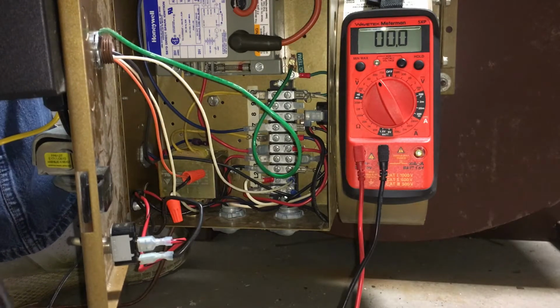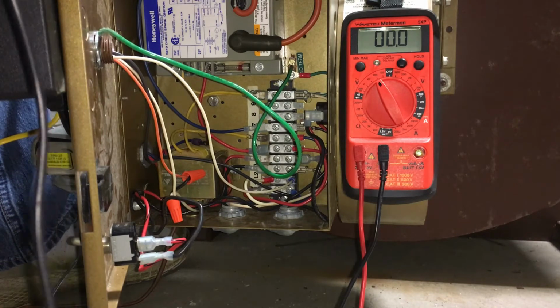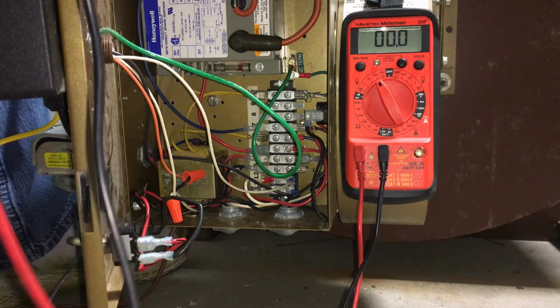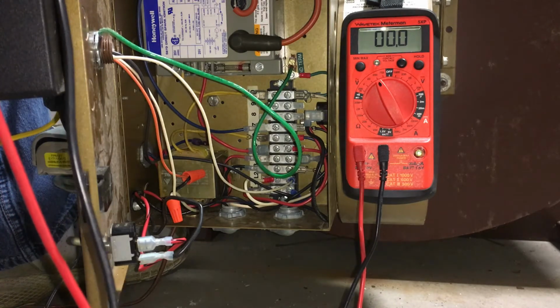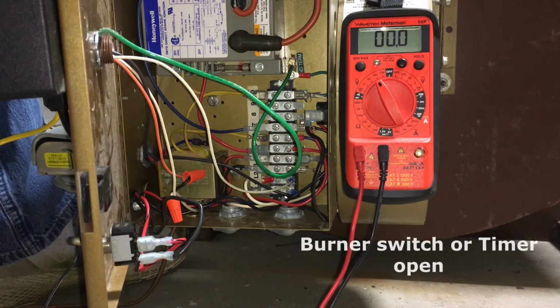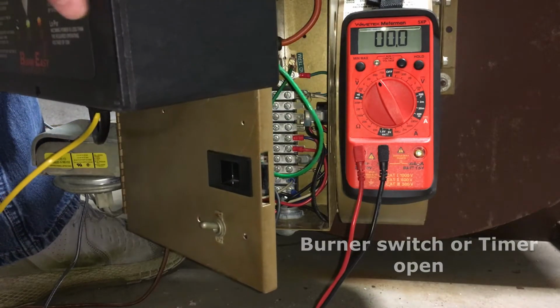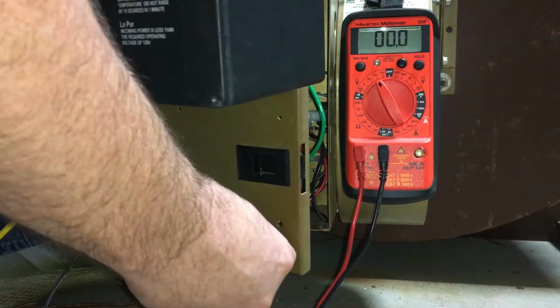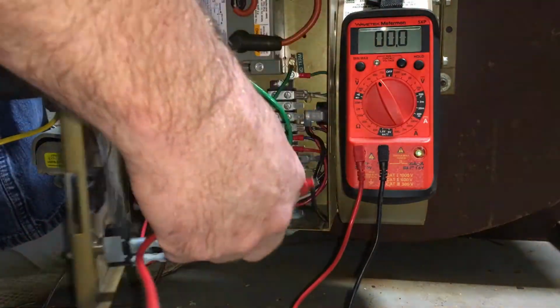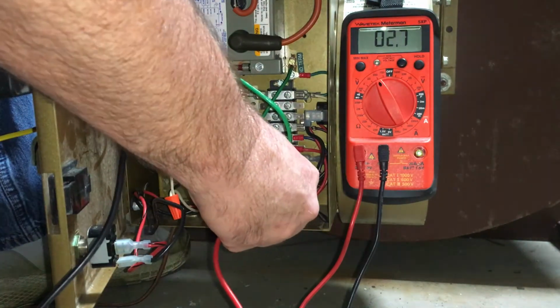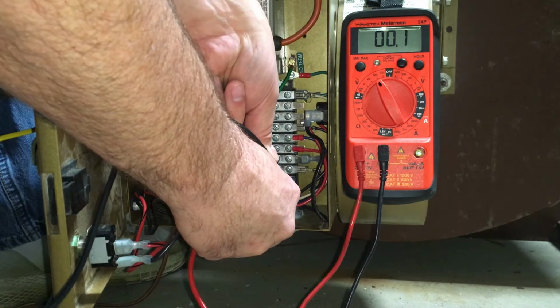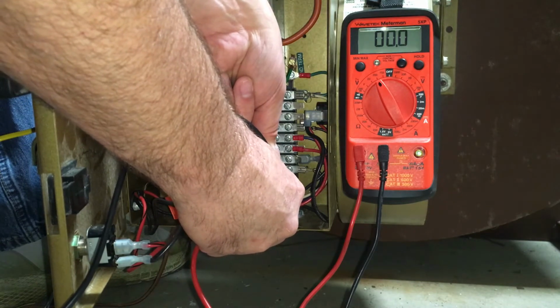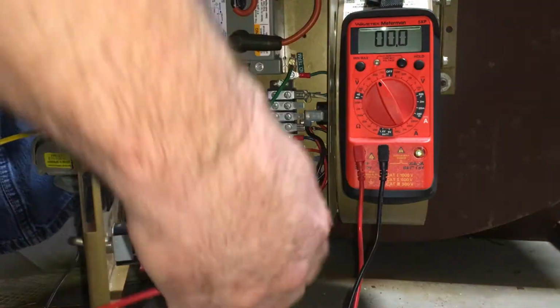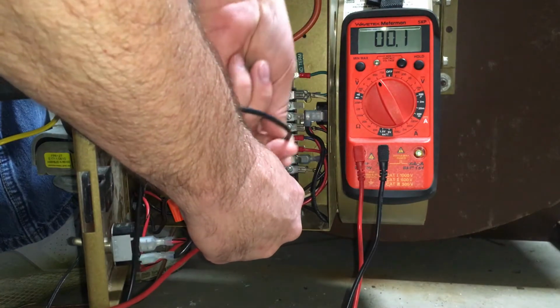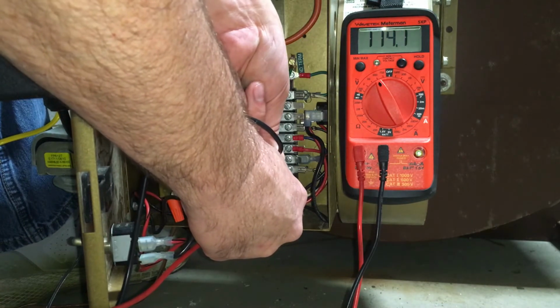Again, if the motor will not run, you've gone through steps 1 and 2. Step 3 verifies L2 and 4, to verify you have proper voltage. If not, that indicates a burner switch or the timer is open. As I turn the unit on, I will shut the main switch off, and again we check between L2 and L4, and I am not getting any voltage through it. That means the switch may be turned off. So I'll turn the switch on, check L2 and L4, and there we are getting our proper voltage.